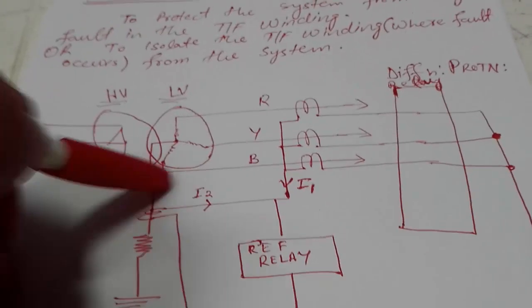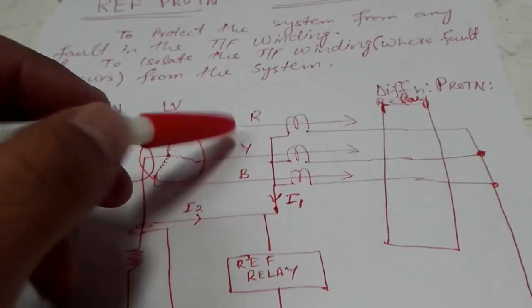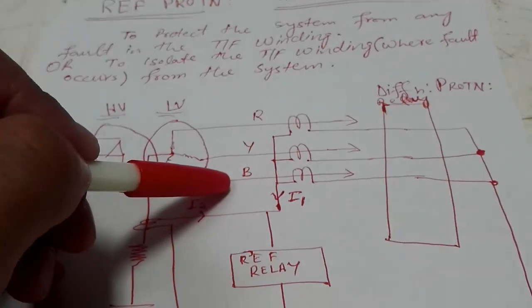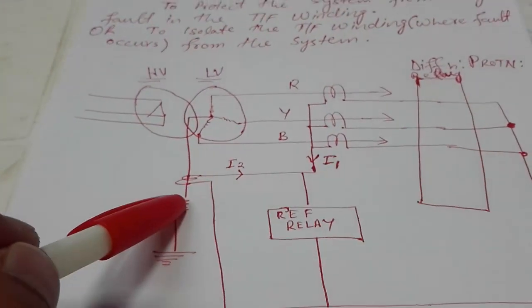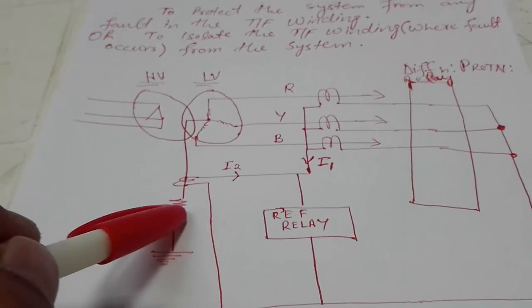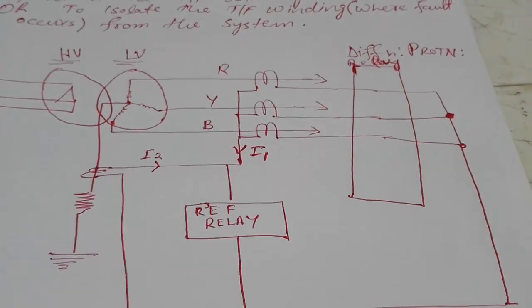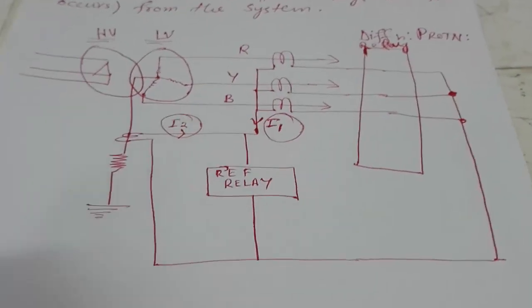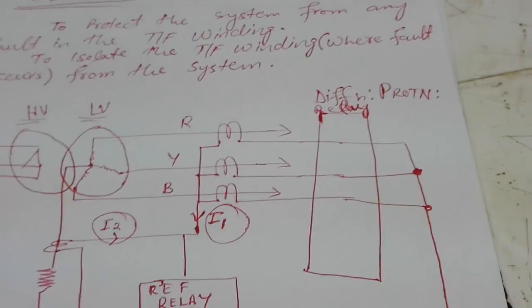For example, we have one delta-star transformer and this is the LV side. Each yellow, blue phase has a separate CT connected to it, and similarly we have one CT connected to the neutral, which is earthed. In normal condition, as we know, there will be balanced flow of current.